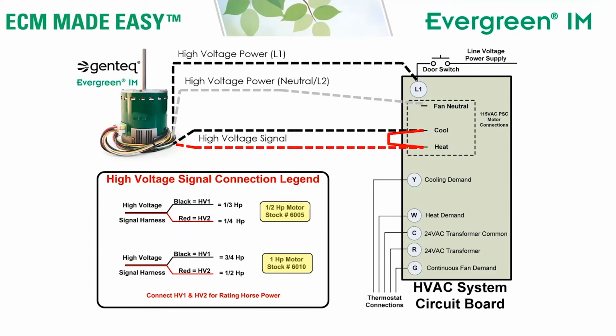If I want to lower the horsepower rating to match the motor I took out, if I connect only the black wire to heat and cool, my half horse motor now runs at 1/3 and my 1 horsepower motor now runs at 3/4.